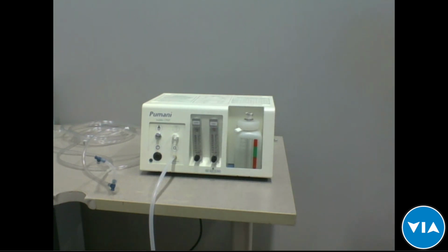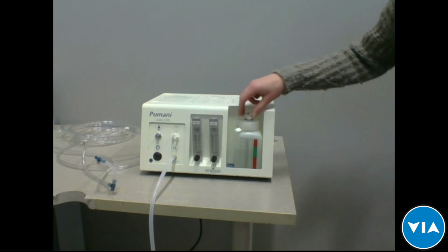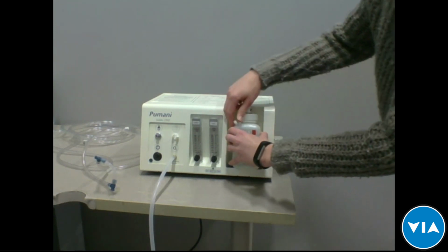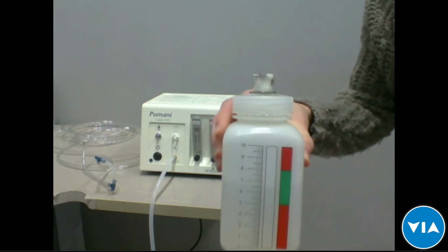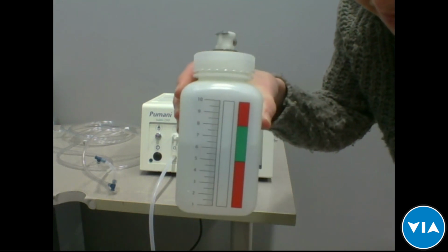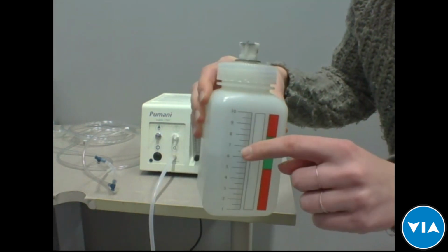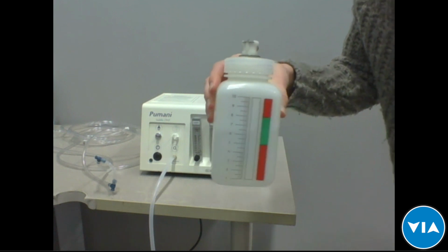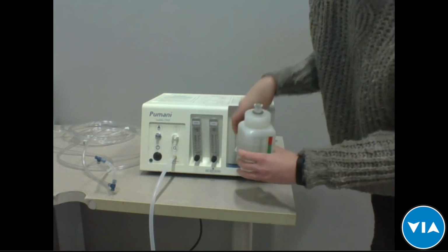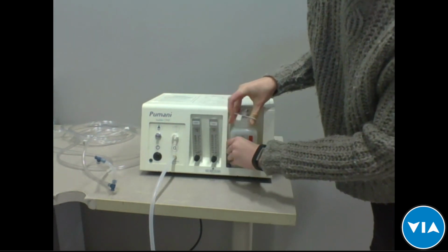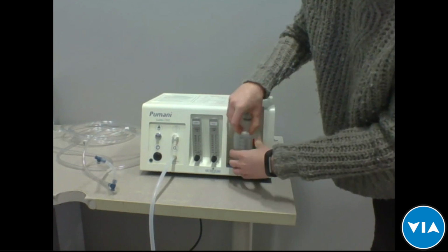So basically, you have the Pumani CPAP in front of you, you can all see. And the first step to do, because it is a bubble CPAP, is to fill the bottle with water. And the usual recommendation is 7 centimeters of water. Anywhere between that green line is okay. And once again, it's according to your protocols in your hospital and in Ghana. So once that's full, you connect it.